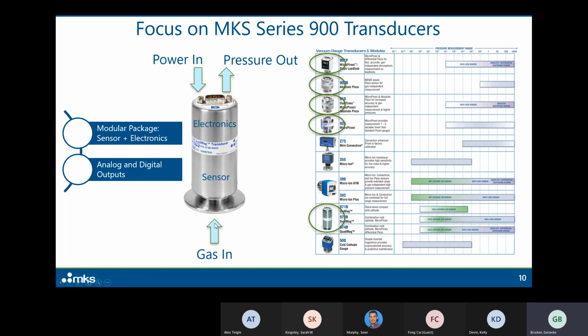And they're true transducers. Gas comes in with its pressure, and a pressure signal comes out. All you have to do is mount it on the vacuum system, apply some power, and a signal comes out, which you can choose. You can pick up an analog signal or a digital output from these devices, and this is how you get your pressure measurement. Okay? And as you can see, here's the pressure range. We cover a very wide range, all the way from ultra-high vacuum to atmosphere with these small devices.